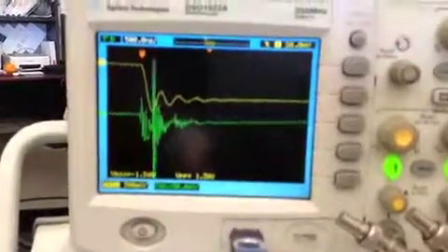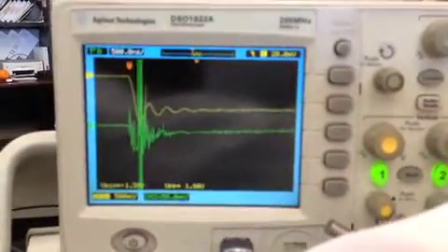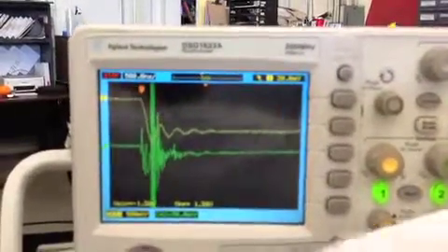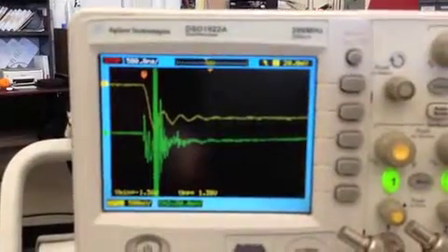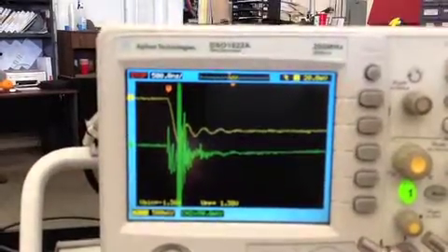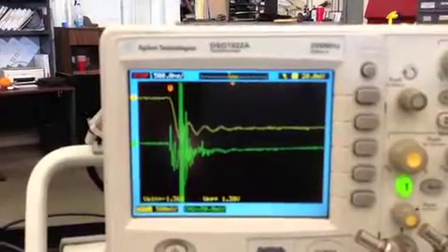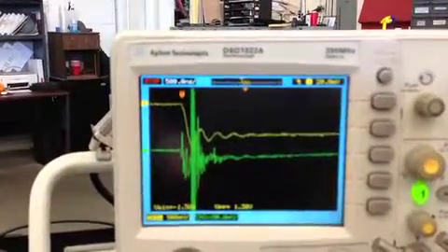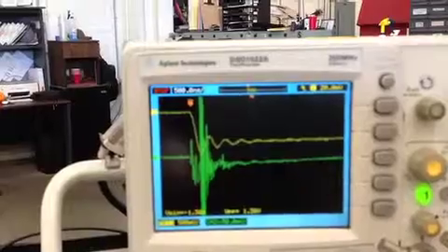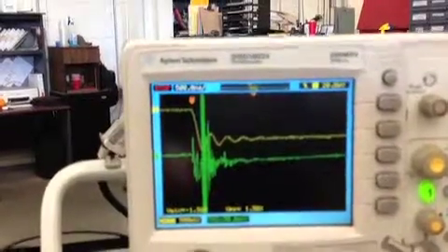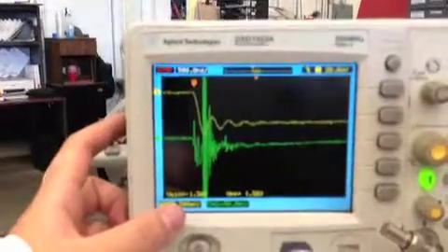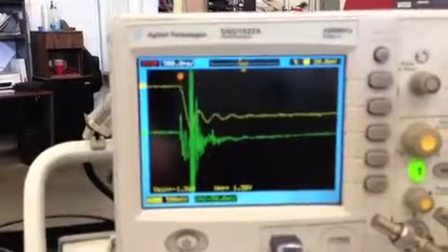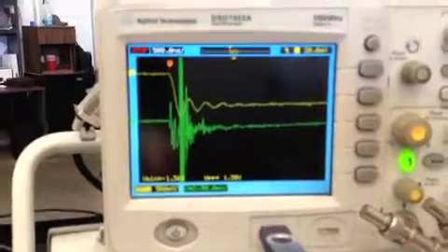We'll try it again here. So this is telling us that we have the partial discharge. The high green bar is occurring at a low point on the yellow graph, and that's going to tell us what voltage we have. Right now it's 2720 volts. So here, this test shows a trip at 2720 volts.